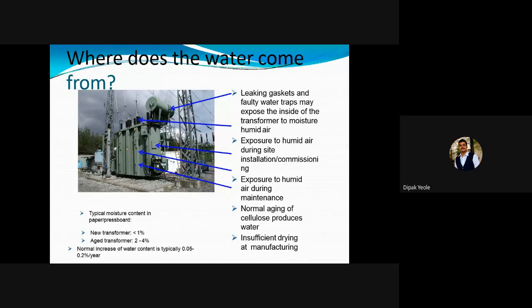Water can come from leaking gaskets, and faulty water traps may expose the inside of a transformer to moisture and humid air. The gaskets are available, and because of this there can be leakage in these gaskets, along with exposure to humid air during site installation and commissioning.